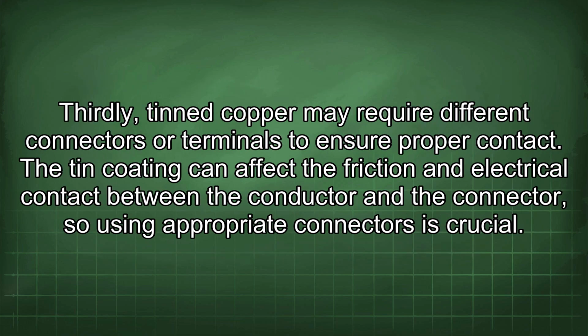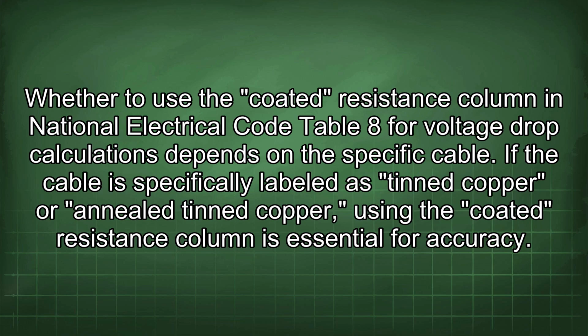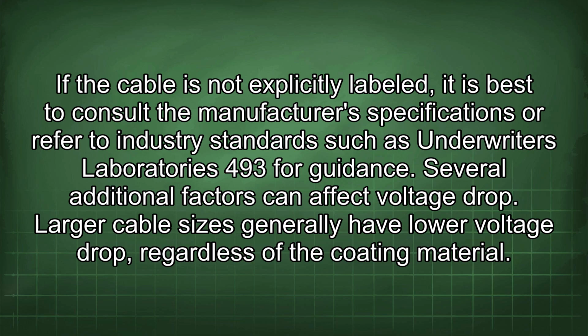Thirdly, tinned copper may require different connectors or terminals to ensure proper contact. The tin coating can affect the friction and electrical contact between the conductor and the connector, so using appropriate connectors is crucial. Whether to use the coated resistance column in National Electrical Code Table 8 for voltage drop calculations depends on the specific cable. If the cable is specifically labeled as tinned copper or annealed tinned copper, using the coated resistance column is essential for accuracy. If the cable is not explicitly labeled, it is best to consult the manufacturer's specifications or refer to industry standards such as Underwriters Laboratories 493 for guidance.